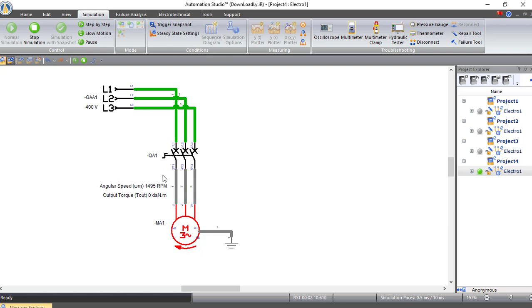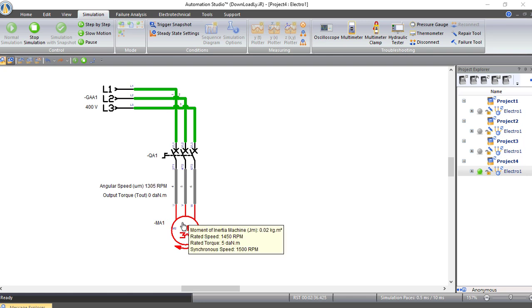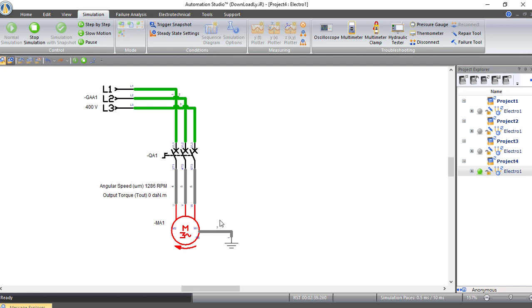Now, what if we want to make the motor rotate in the other direction — anti-clockwise? We have to swap two wires, making an interchange in the power source connections to the motor. This changes the direction of the rotating magnetic field, which in turn makes the rotor rotate in the other direction. Let's create this circuit.